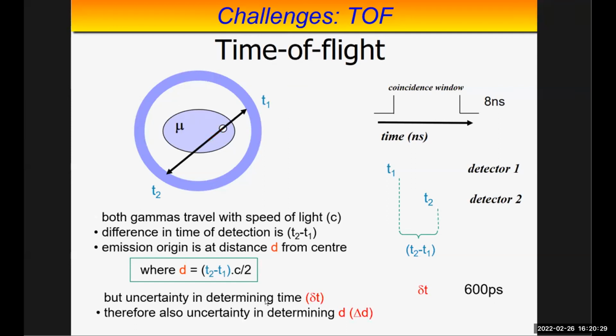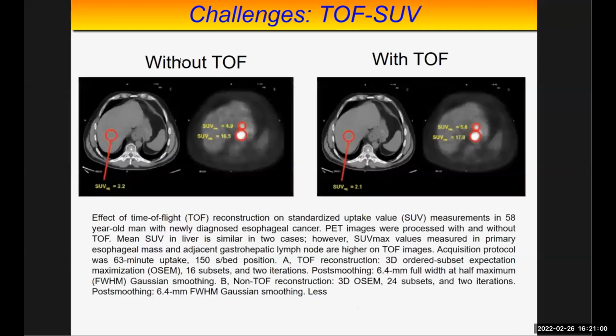But the uncertainty in determining time is delta T. Therefore, the uncertainty in determining D is also delta D. So you can see here that if you know delta T, you can calculate the uncertainty, and that is 9 centimeters. By improving the timing resolution, that is by decreasing delta T, you can reduce the uncertainty. This is an example where we have not applied time of flight, showing SUV values lower than in the image reconstructed using time of flight.